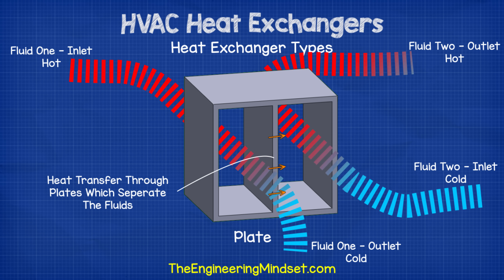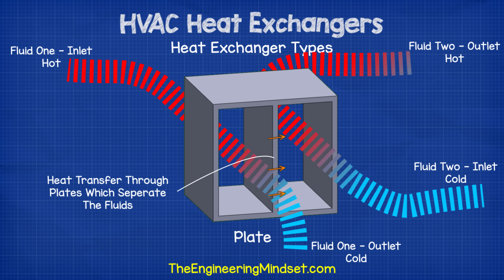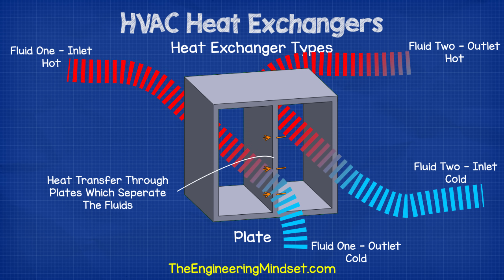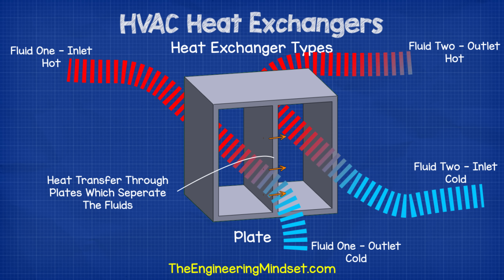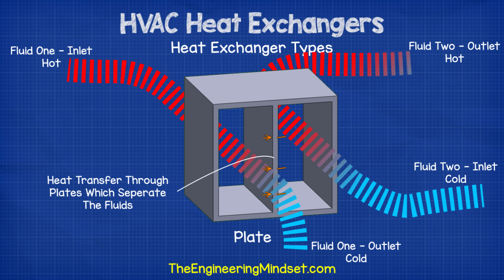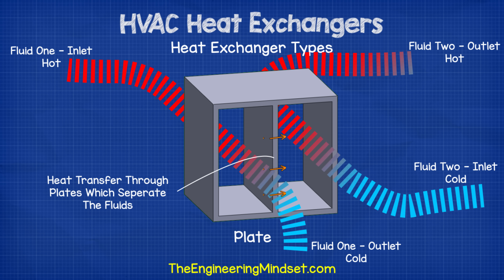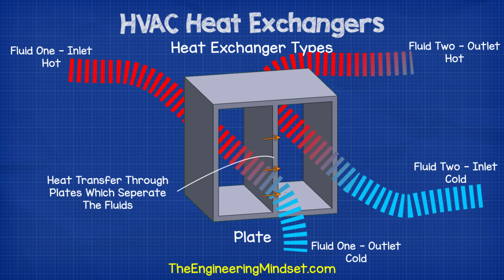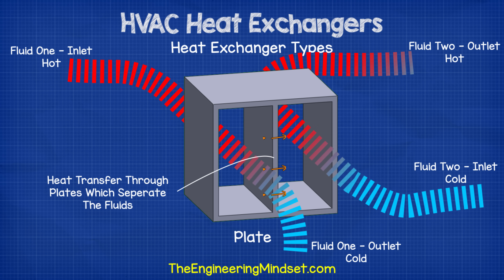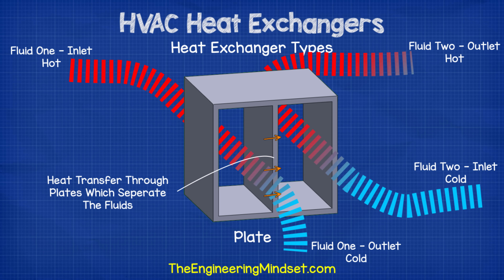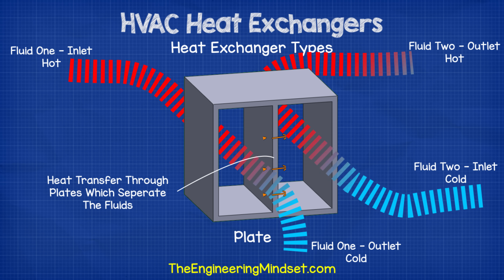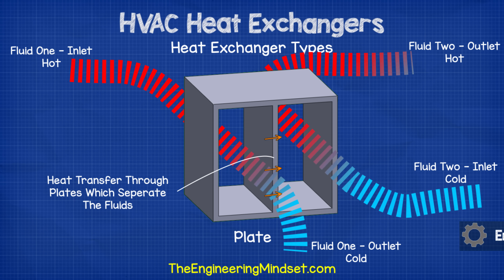Plate heat exchangers use thin plates of metal to separate the two fluids. The fluids generally flow in opposite directions to improve the heat transfer. The heat of the hottest fluid is convected onto the plate wall and conducted through to the other side, and the other fluid entering at a lower temperature then carries it away through convection.